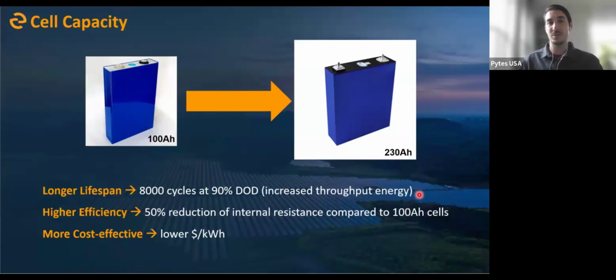It's essentially 2,000 additional cycles compared to all of our other products, and that gives us a higher, increased amount of energy throughput. What I mean by energy throughput is the total amount of energy in kilowatt hours you can put into or take out of the battery during its lifespan. Our V5 battery, for example, at half the capacity of the V10, a 5 kilowatt hour battery, had a total energy throughput rating of about 19 to 20 megawatt hours per our warranty throughout its whole life. The V10, however, now has a 60 megawatt hour throughput rating. So even though it's twice the capacity of the V5, the throughput warranty is actually over 3 times as much.